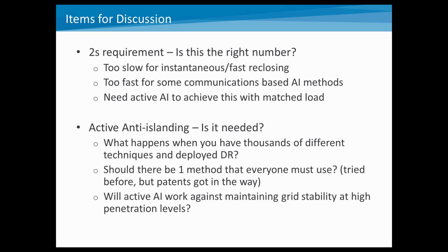The other thing about 2 seconds is it may actually be too fast for some communication-based methods. So some of the phasor-based methods or other communication-based methods may require more than 2 seconds to determine if an island is occurring. And the third point there is the need for active anti-islanding to achieve this number. So 2 seconds is probably only going to be achieved with active anti-islanding. And so these are things just to think about. Obviously, we want to be able to detect unintentional islanding, but the requirement for speed there is something that we probably should address as we see more and more distributed generation set points being opened up for larger voltage and frequency windows.